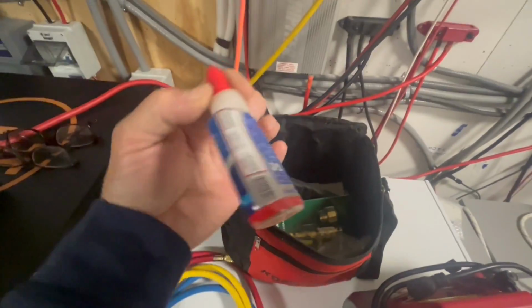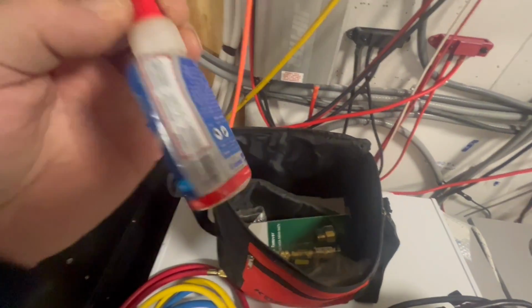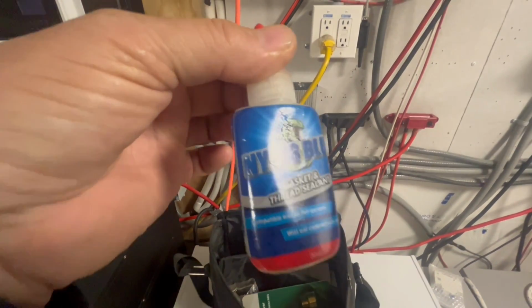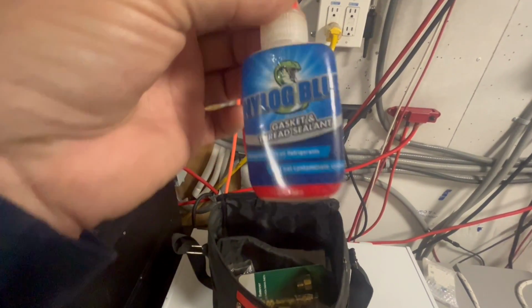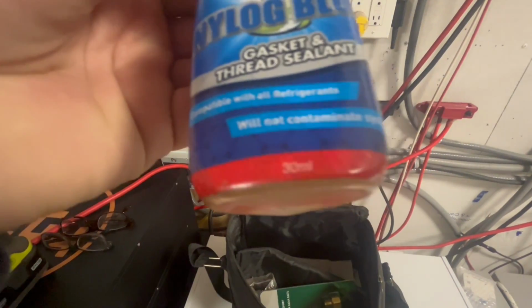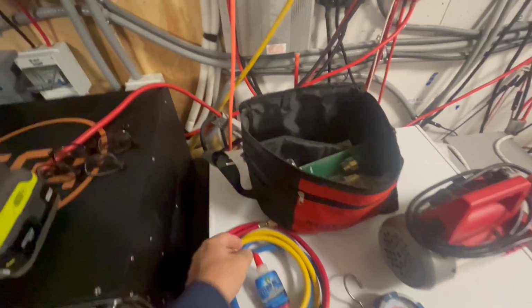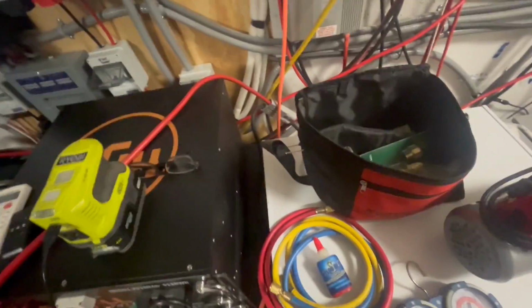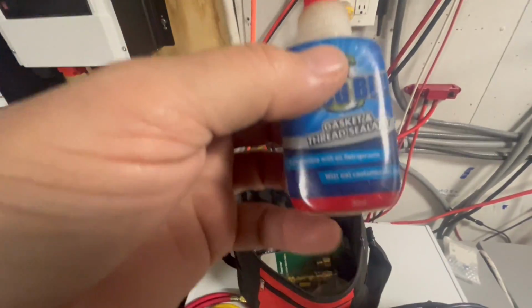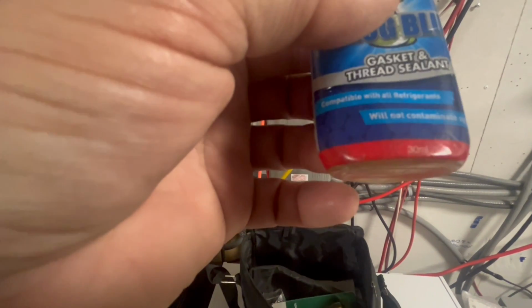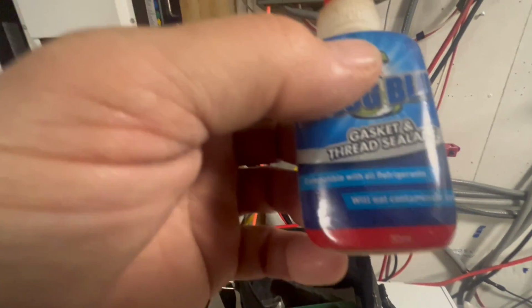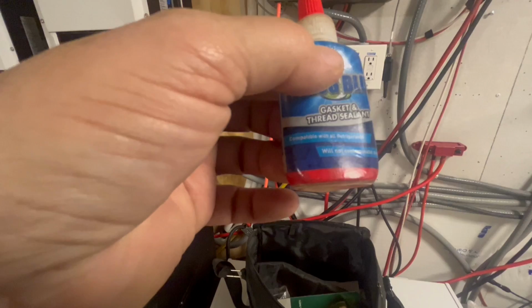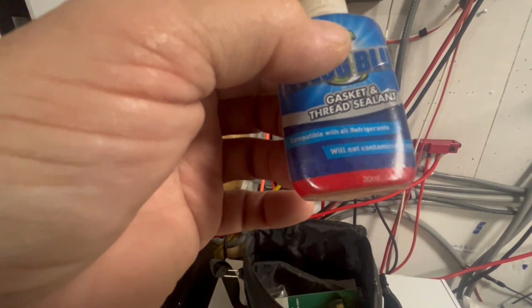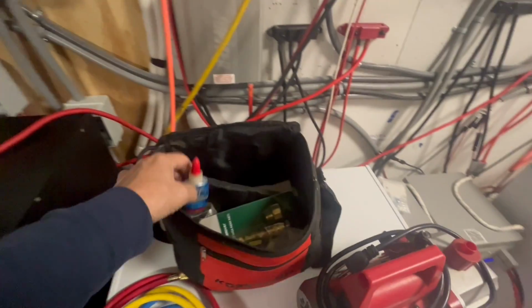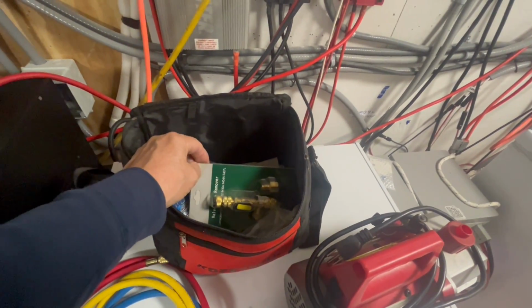It's maybe 18 to 20 bucks a tube, but I had enough in one of these bottles to do like 3 or 4 mini splits. That's a 30 milliliter bottle, gasket and thread sealant, compatible with all refrigerants, will not contaminate the system, so you don't have to worry about that.